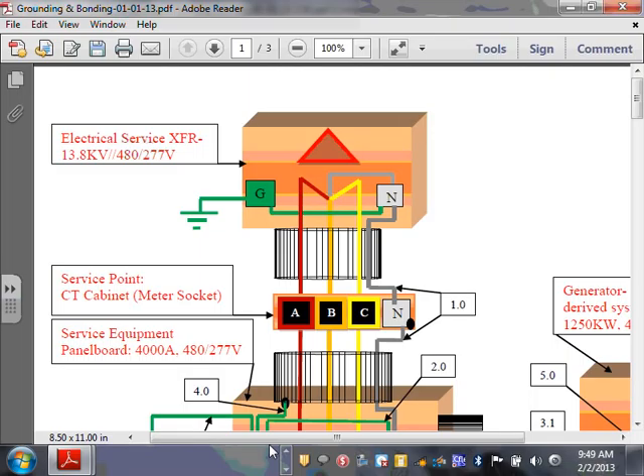Now, if you're a residential guy, you probably don't deal with that. So that little deal here, just drop it. Imagine this does not exist, and you pull your neutral all the way into your service. That's the only difference. It goes into a meter. This will be your meter socket if it's up to 400 amp or less, I believe. That's when they start putting it. So 200 is very typical. A 200 amp meter, that will be your meter socket. Any comments about these two coming in?